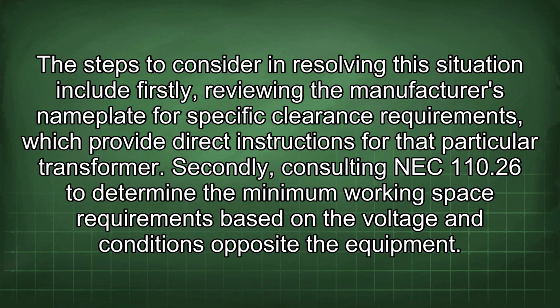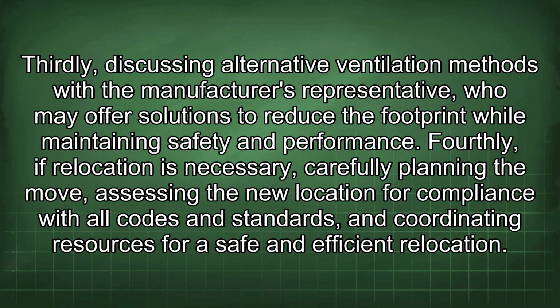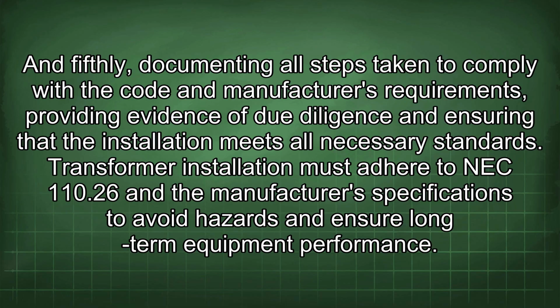The steps to consider in resolving this situation include, firstly, reviewing the manufacturer's nameplate for specific clearance requirements, which provide direct instructions for that particular transformer. Secondly, consulting NEC 110.26 to determine the minimum working space requirements based on the voltage and conditions opposite the equipment. Thirdly, discussing alternative ventilation methods with the manufacturer's representative, who may offer solutions to reduce the footprint while maintaining safety and performance. Fourthly, if relocation is necessary, carefully planning the move, assessing the new location for compliance with all codes and standards, and coordinating resources for a safe and efficient relocation. And fifthly, documenting all steps taken to comply with the code and manufacturer's requirements, providing evidence of due diligence and ensuring that the installation meets all necessary standards.